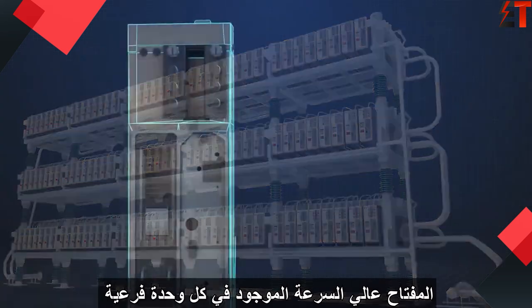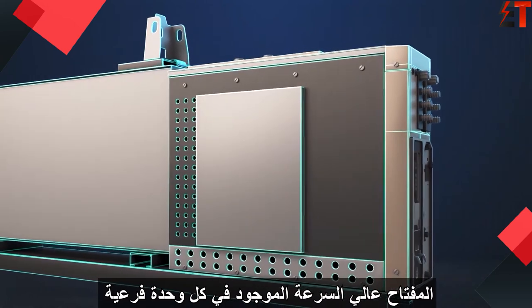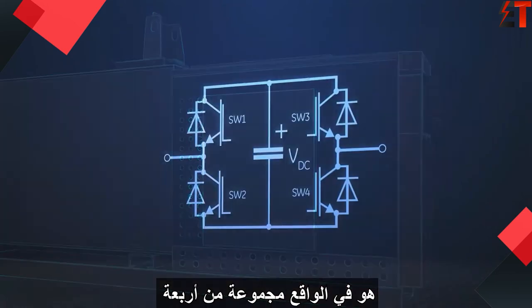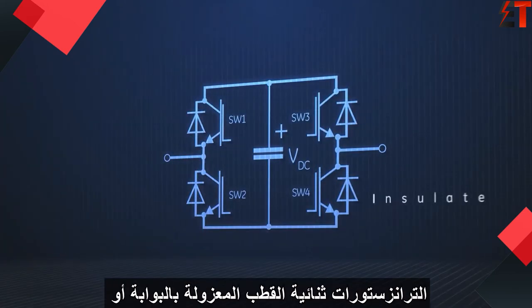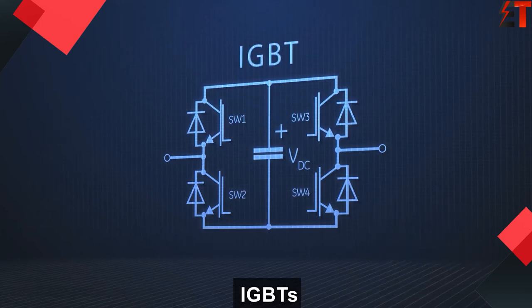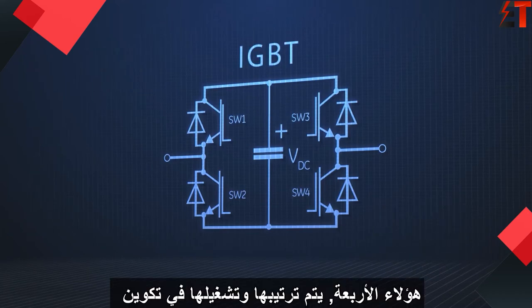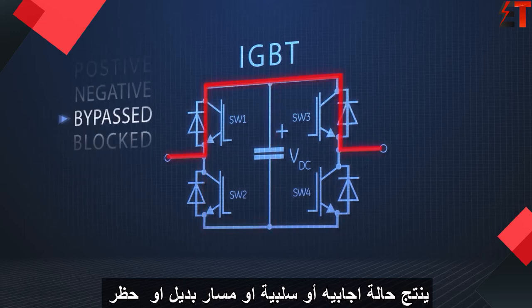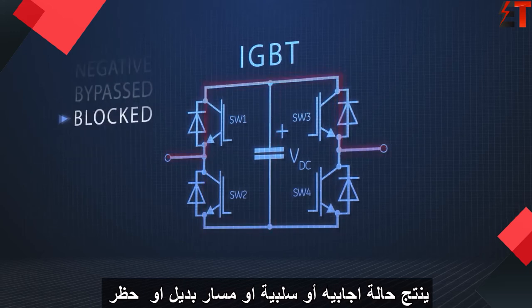The high-speed switch in each sub-module is actually a set of four power electronic devices called insulated-gate bipolar transistors, or IGBTs. These four IGBTs are arranged and operated in a configuration that produces a positive, negative, bypassed, or blocked state.